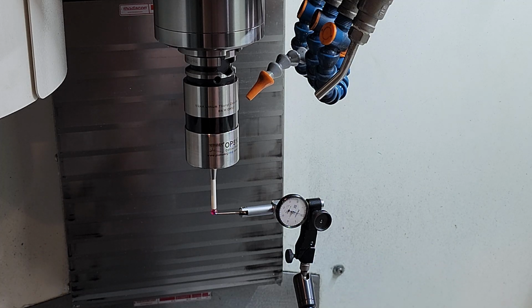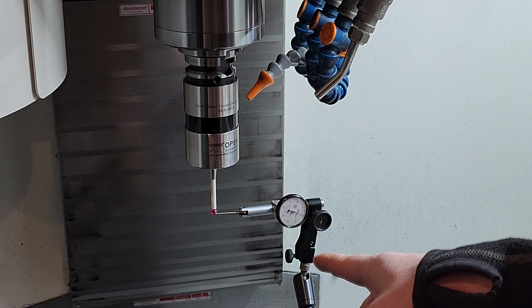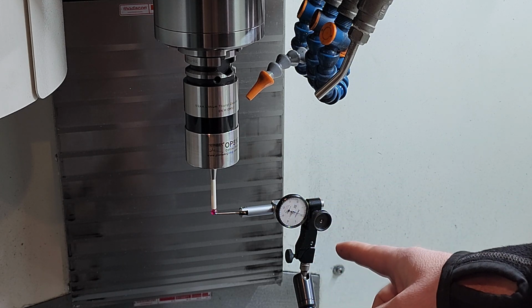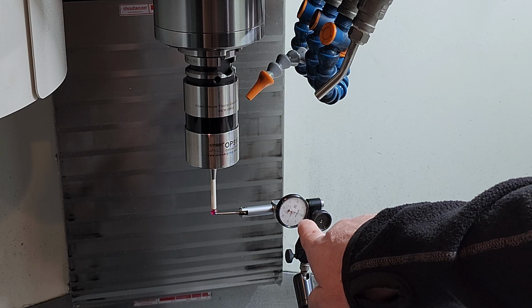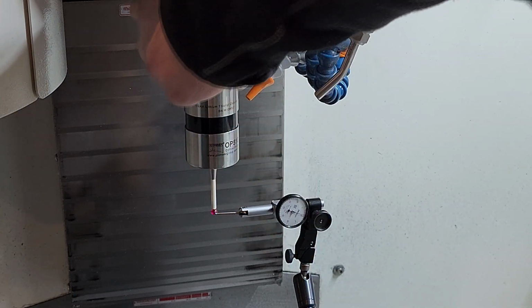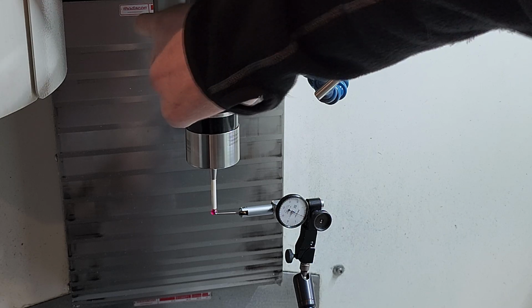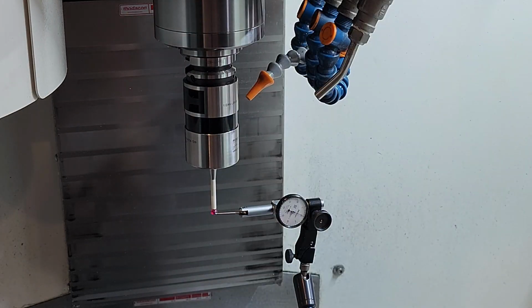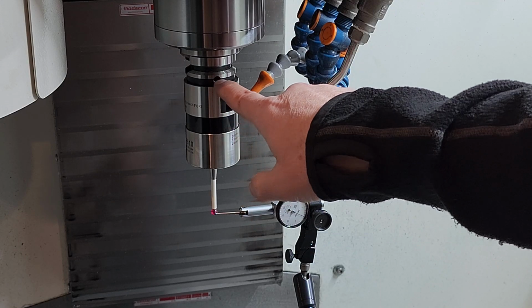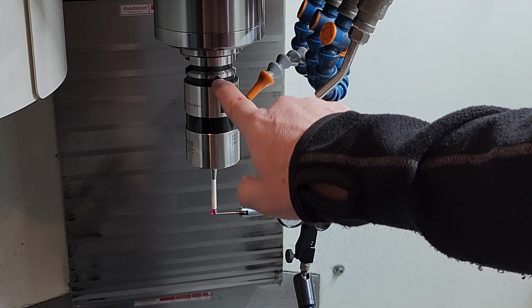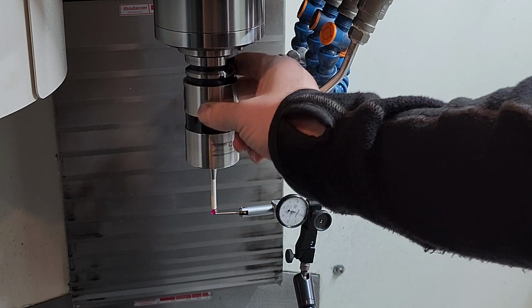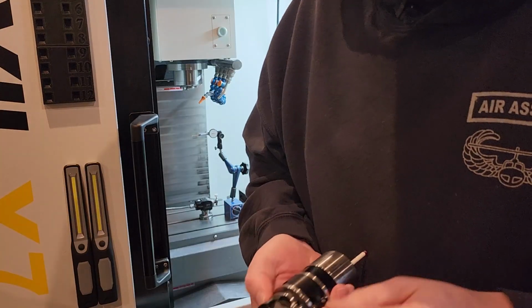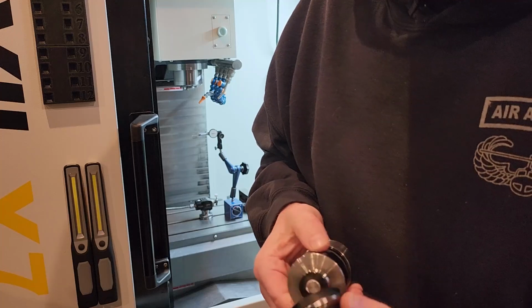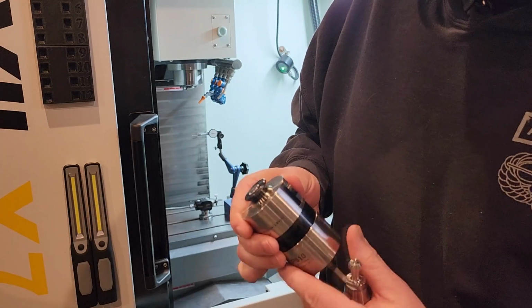Note the position of the magnetic base and dial indicator. In this configuration, we can measure the run out of the ruby as the spindle is slowly rotated. The current run out of my probe is about 0.001 inches or 0.0254 millimeters. That is nowhere near the accuracy called out in the book and will need to be adjusted. To adjust the run out, we need to adjust 3 screws. These screws not only allow us to adjust the run out, but they also mount the probe to the BT30 shank.